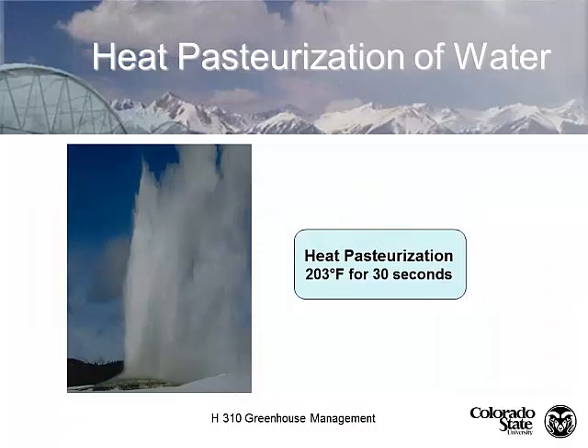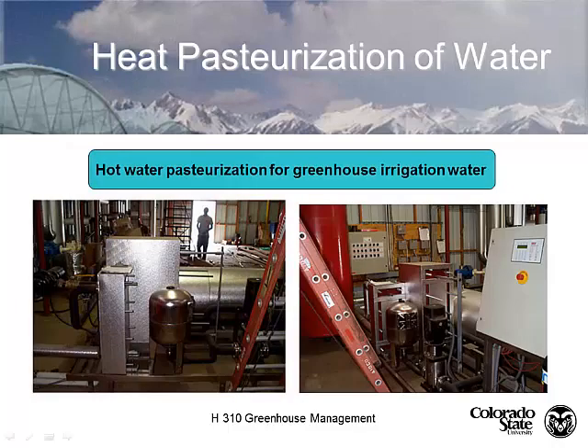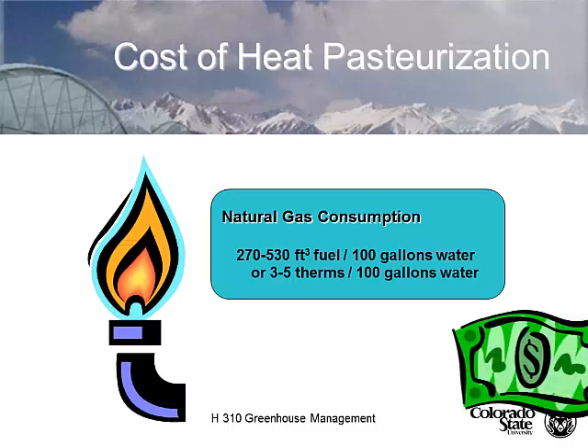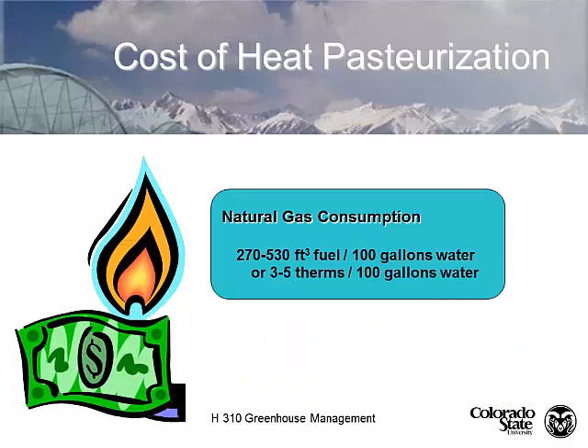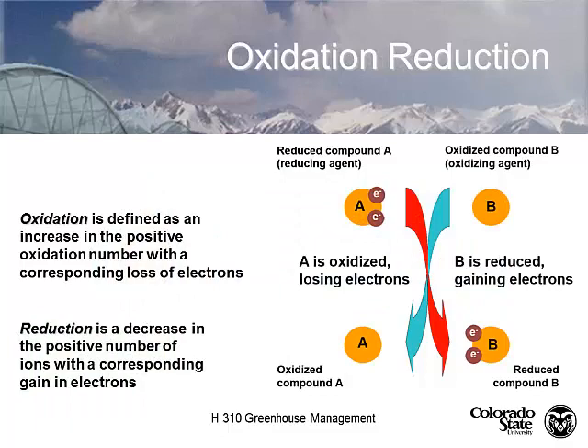In Europe, many growers use heat pasteurization — heating water to 203°F for 30 seconds kills most organisms. This is attached to a steam boiler. However, it requires 270 to 530 cubic feet of natural gas per 100 gallons of water, or three to five therms, so it's very expensive. A lot of people in the United States don't use heat pasteurization because of fuel costs, though it does work.